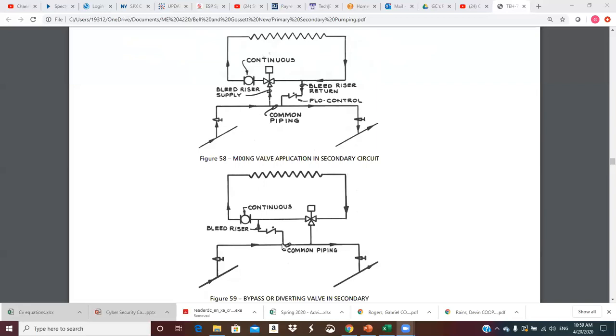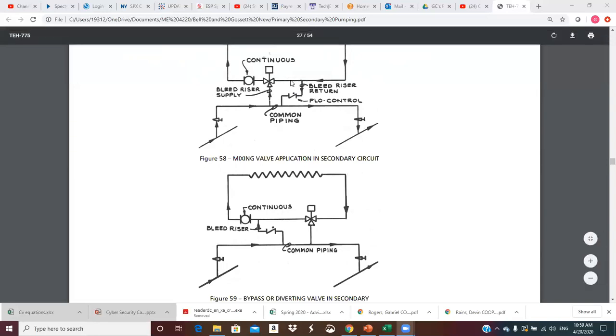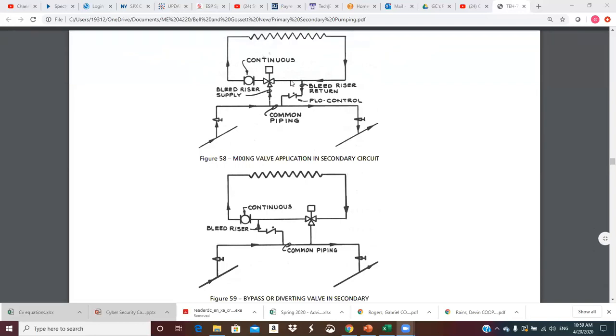In this case the flow is blocked in the other direction. So if the system is shut off and we're just circulating and the water cools down, that water can contract and we can get a very low pressure on this side, which can contribute to pump cavitation. We'll talk more about that later.